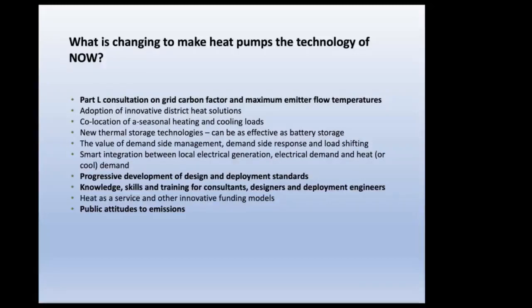Progressive development of design and deployment standards is really about making sure we are designing new installations to suit heat pumps, moving away from the conventional 82-71 flow and return temperatures, moving towards potentially a 60-40, with 65-45 being ideal as well.